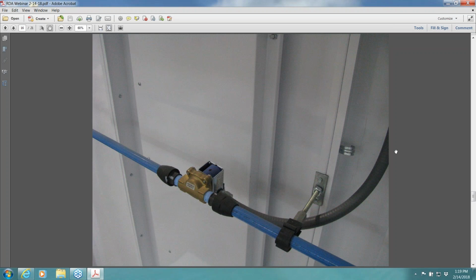The other problem is there's one safety device you'll see in that picture here, right in the middle. This is a solenoid valve. There are various codes that talk about having to have the airflow on in the booth before they'll allow compressed air to flow to the spray gun. What they're trying to do is make sure your painter's not in there painting without ventilation. So you have to have a solenoid valve installed on the airlines. This gets missed a lot, or it gets put as the very last thing in the project, and you're totally done and ready, and then all of a sudden you realize the compressed air isn't done, or it's done and doesn't have a valve, and you fail an inspection because you don't have that connection between your air system in the booth and the compressed air system delivering air to the spray gun.